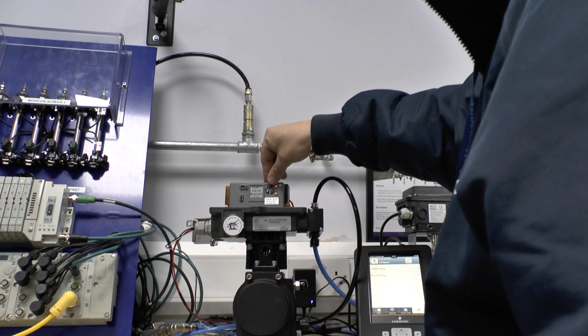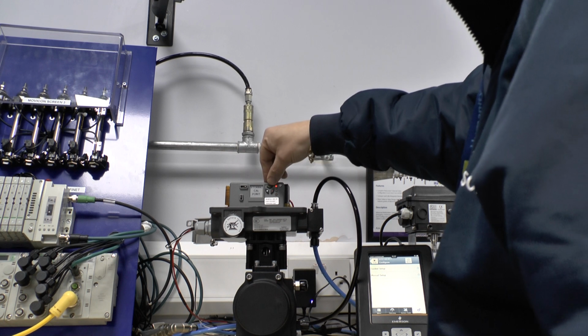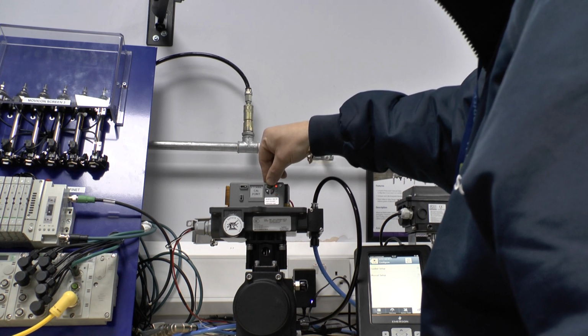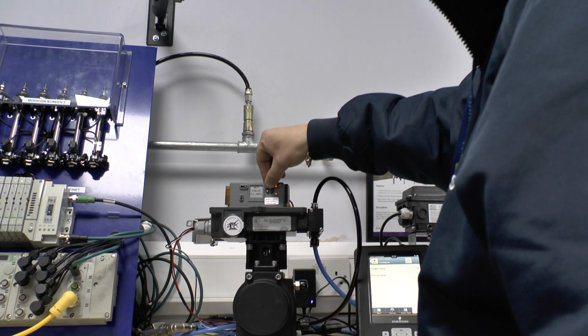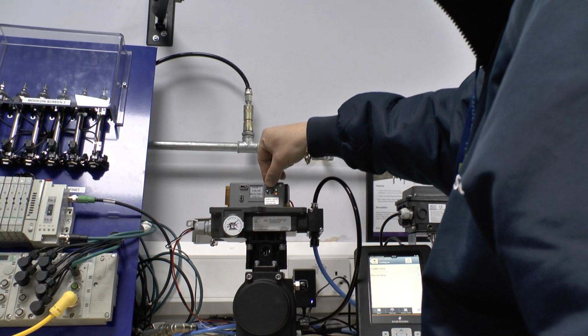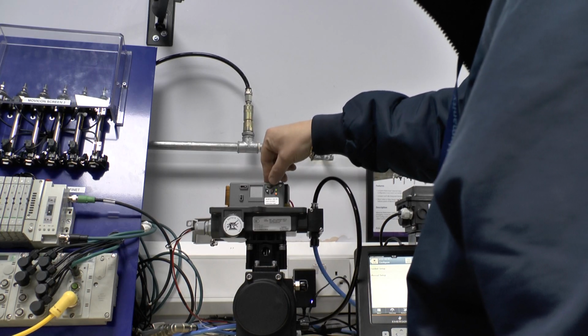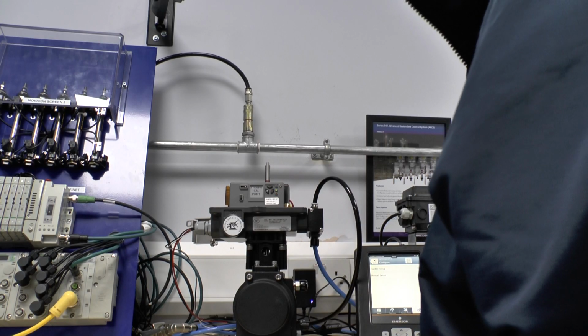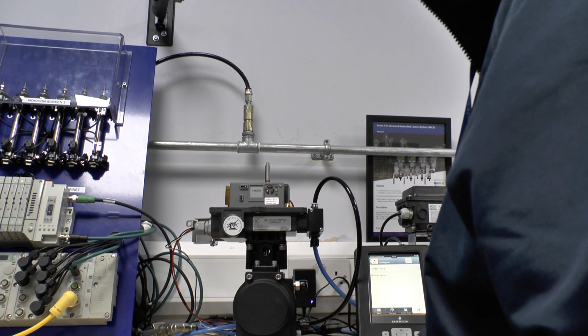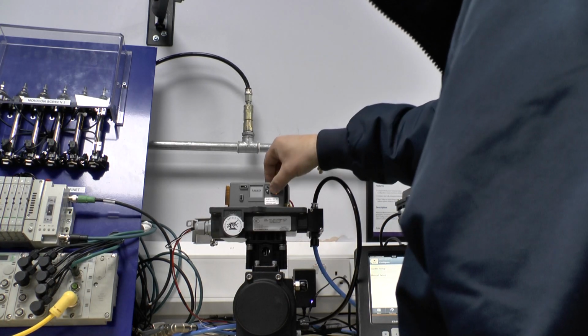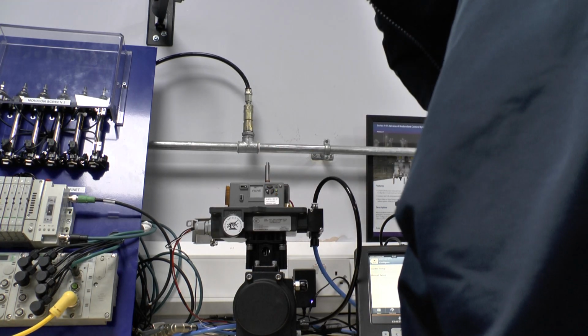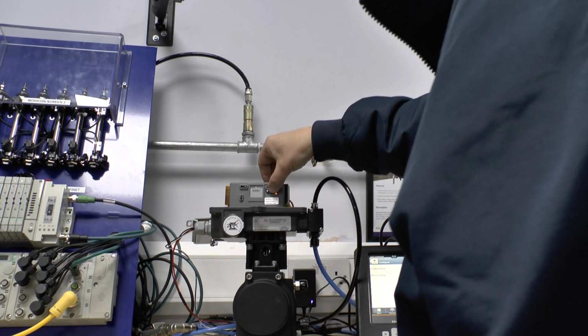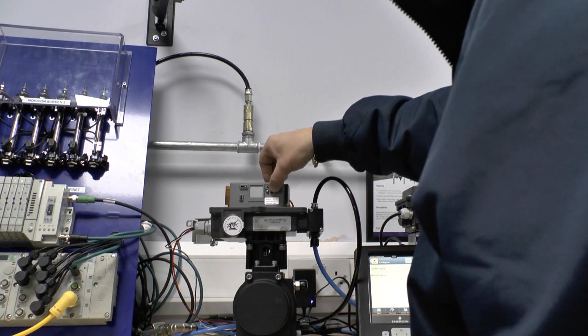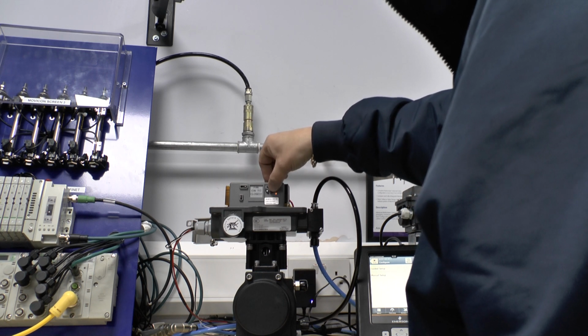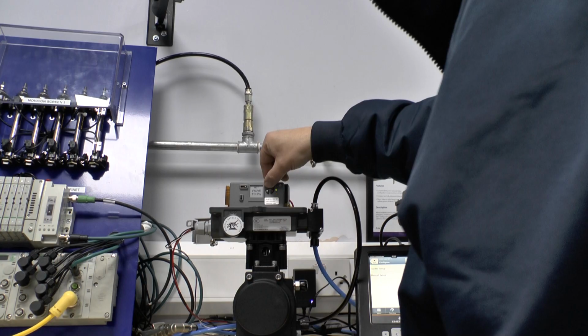Set valve to 0, so we're storing the position. Okay, and now it's gone to 100, storing the position. No, my apologies, I've gone the wrong way there in terms of clockwise or counterclockwise to close, so let me think about this. Are you sure? Yes, fail clockwise to close, that's the one that I need to go to.